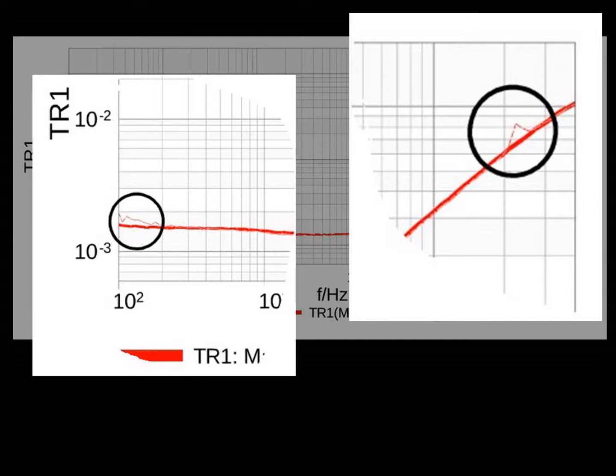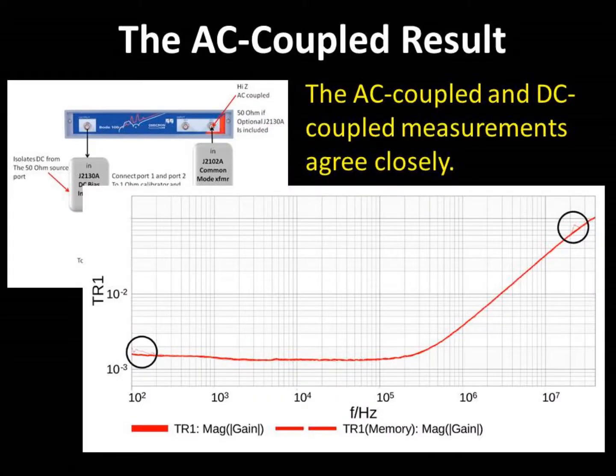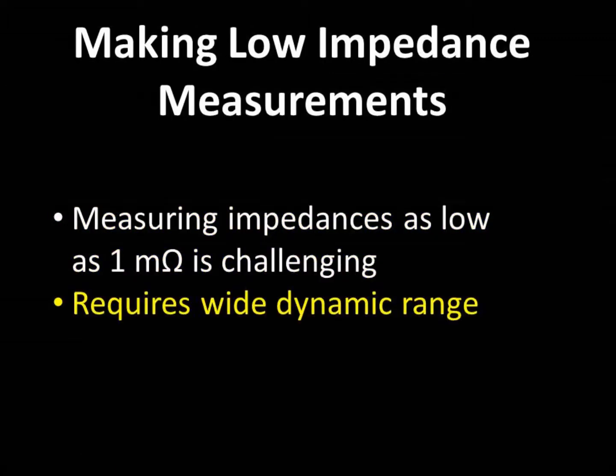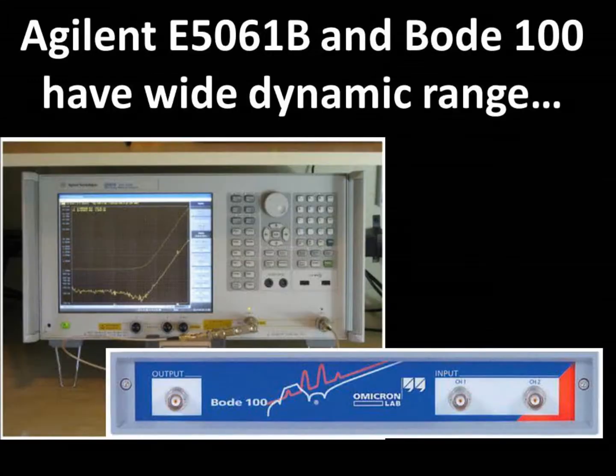Just one final note on the AC-coupled measurements: we found that when the same measurement was taken with the DC-coupled setup, there was very close agreement between the AC-coupled and DC-coupled results. To measure impedances as low as 1 milliohm requires wide dynamic range. The Bode 100 and Agilent E5061B analyzers are impressive in this regard, with both instruments providing approximately 125 to 130 dB dynamic range.